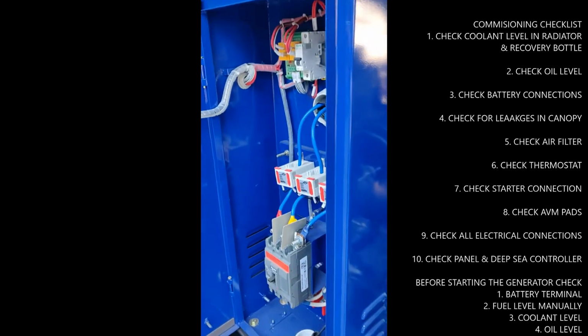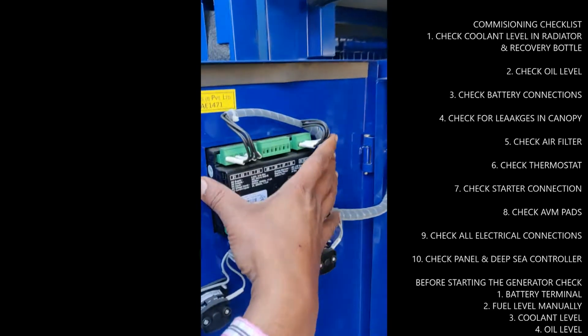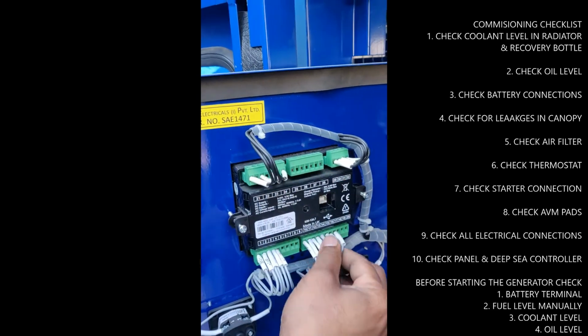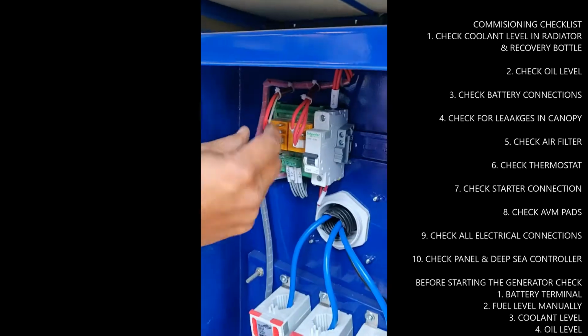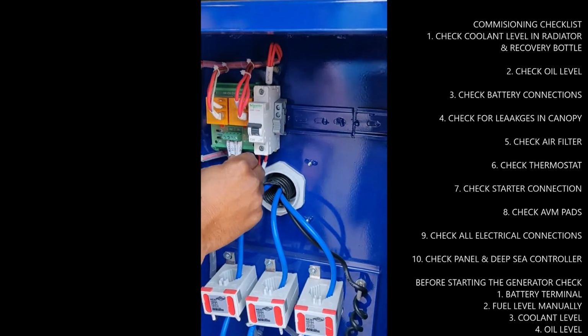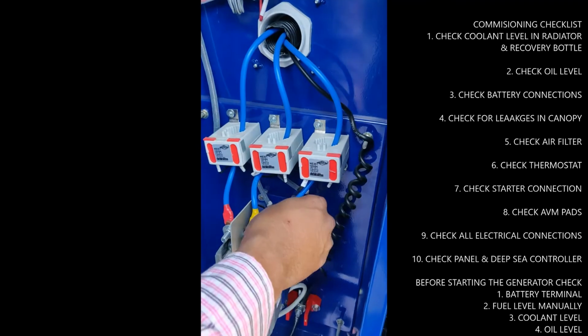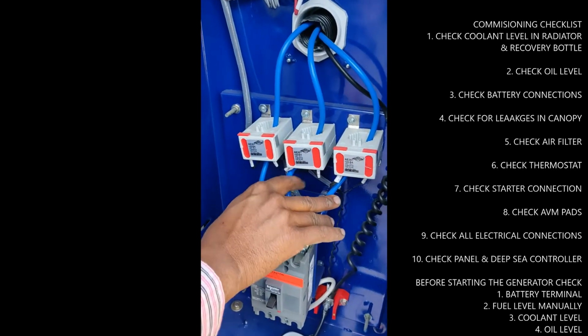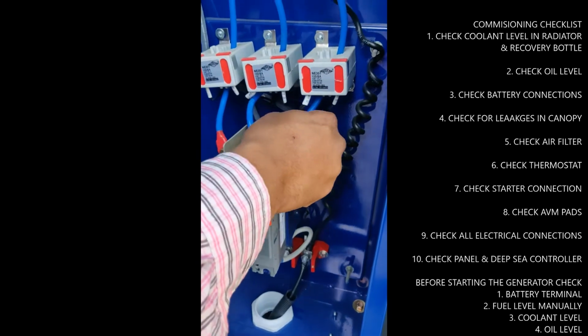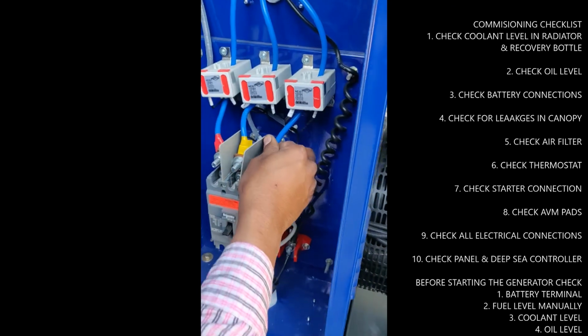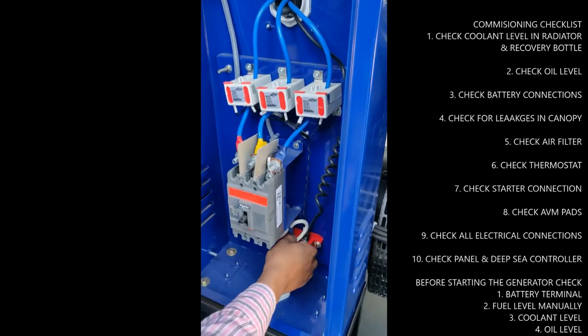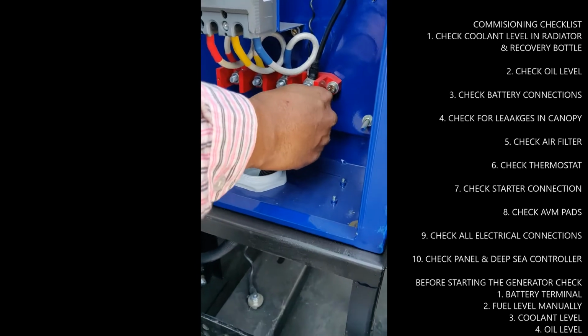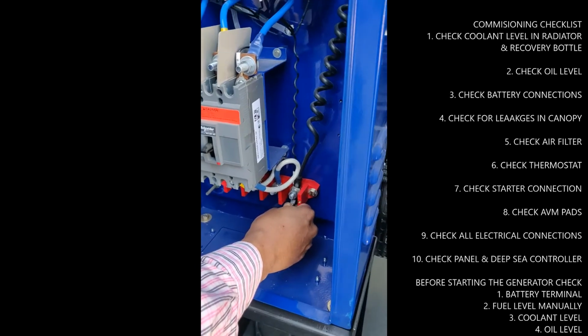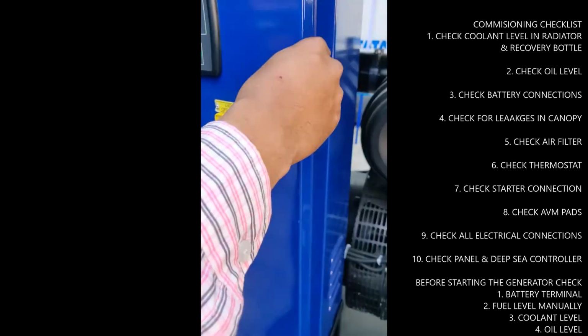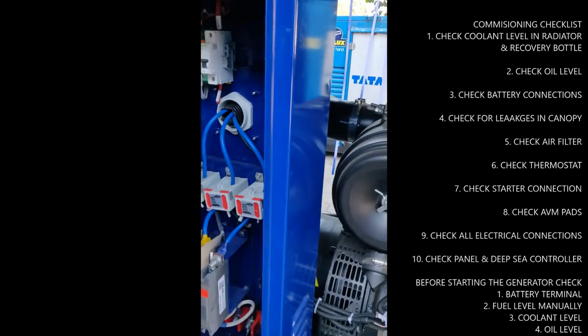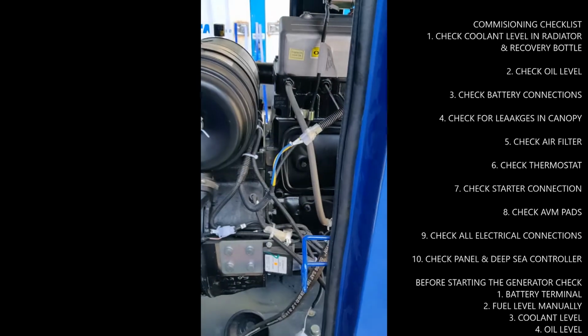Coming to the panel, check that the deep sea connections are all properly done and tight. All connections in the panel, the relay card, the MCBs, all the RYB cables that are coming into the generator from the alternator are tight and properly fitted and not loose at any time. This is the neutral cable which is coming in and goes to the connection of the earthing. Close the panel properly and ensure that it is properly locked.